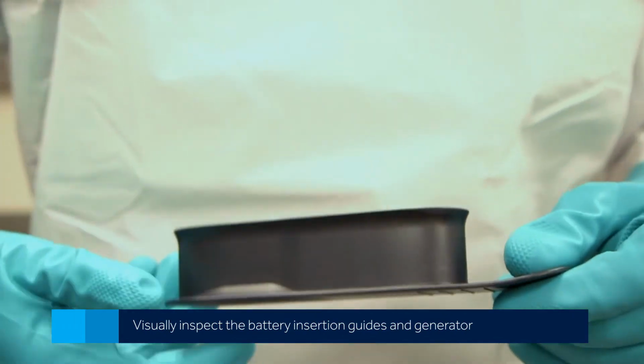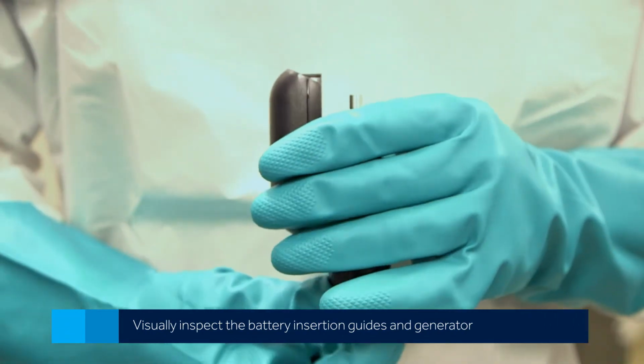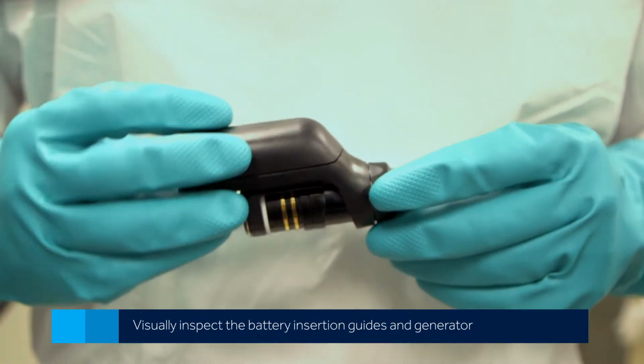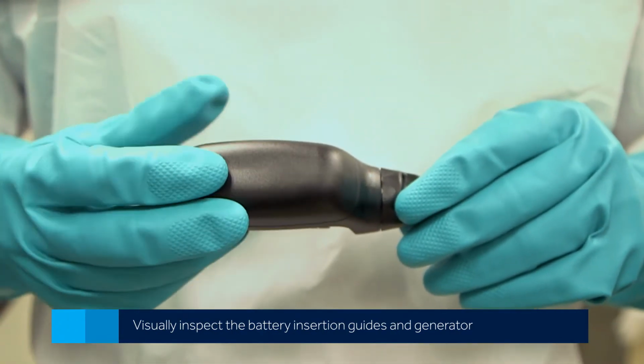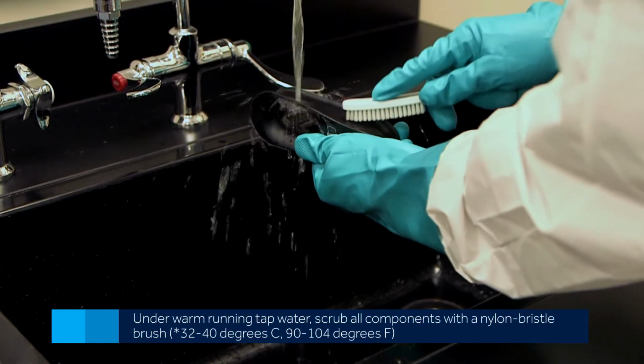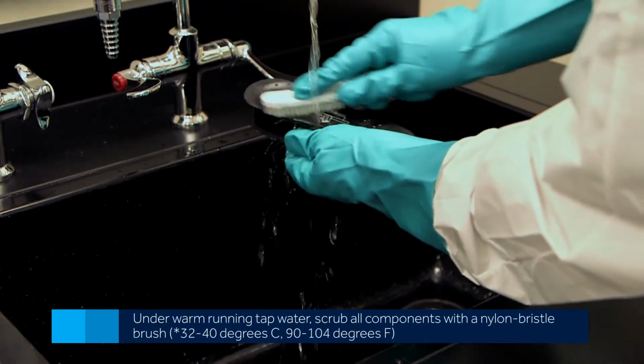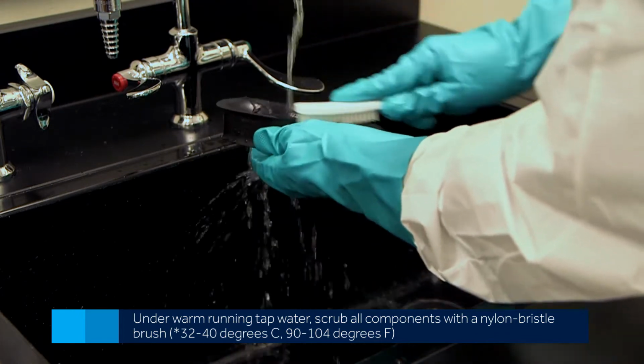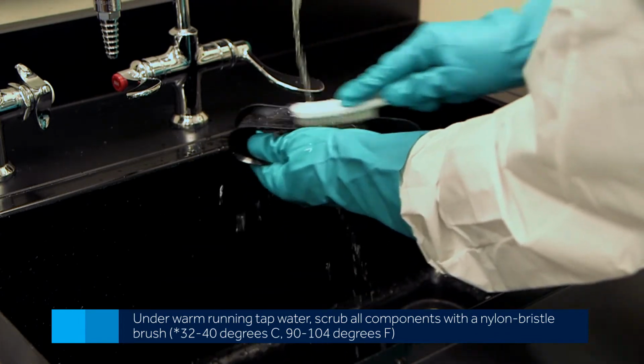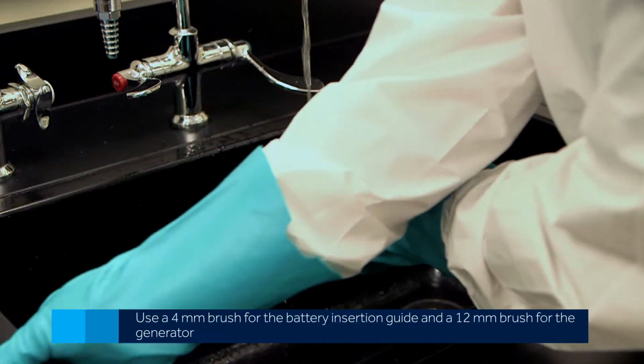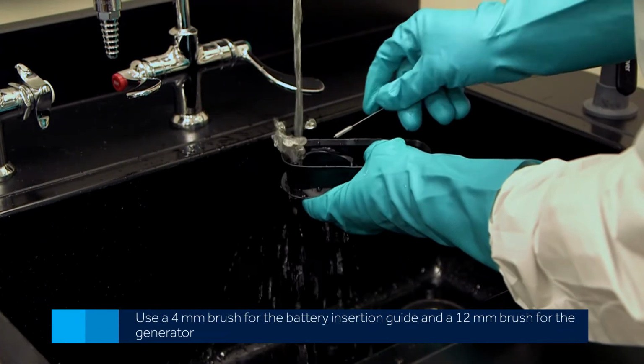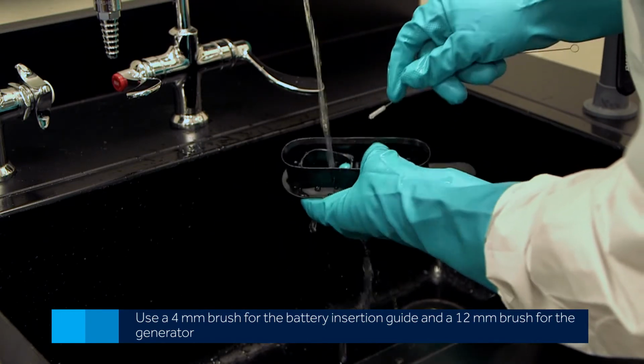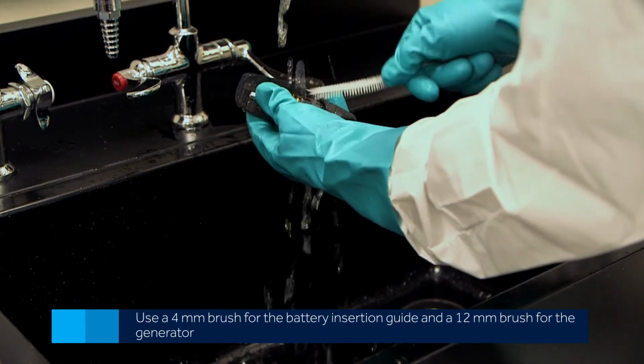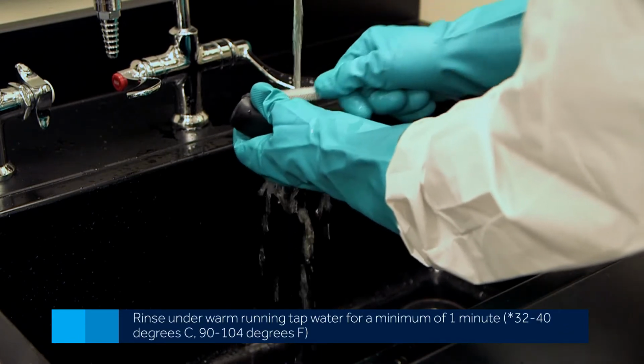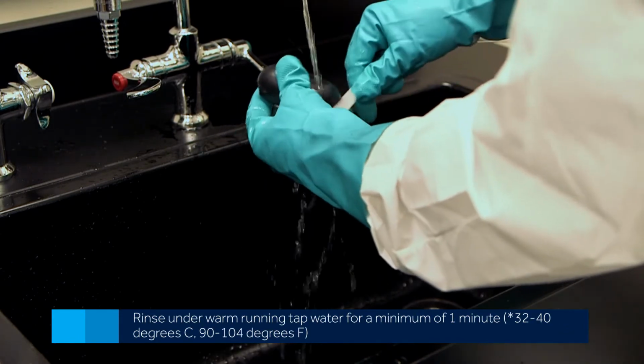To start, visually inspect the battery insertion guides and generator. Do not use the components if they are broken, cracked, nicked, or have any other damage. Replace damaged components. Under warm running tap water, scrub all components with a small, soft, nylon bristled general instrument cleaning brush to remove surgical debris. For hard-to-reach crevices, use a 4 mm soft nylon bristle brush for the battery insertion guide, and use a 12 mm soft nylon bristle brush for the generator. Rinse under warm running tap water for a minimum of 1 minute.